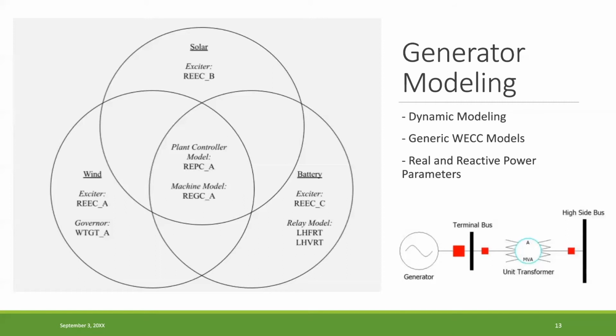To describe a few of the dynamic models shown here in the Venn diagram, we have the renewable energy plant controller and renewable energy generator converter models. These served for our solar, wind, and battery models in our case. A governor model would support a generator to control the flow of power input. The battery had a relay model for voltage and frequency protection. If the voltage or frequency were to deviate, the model would trip the generator so it can prevent damage.